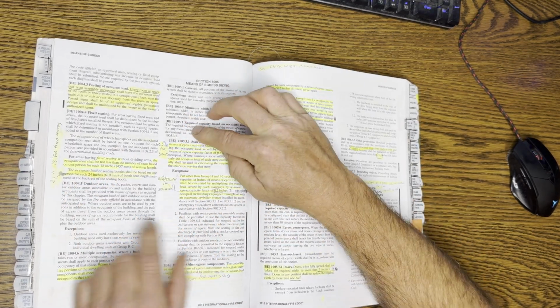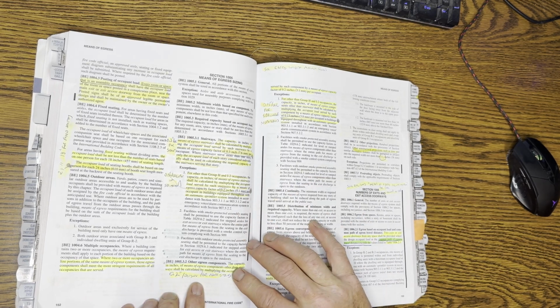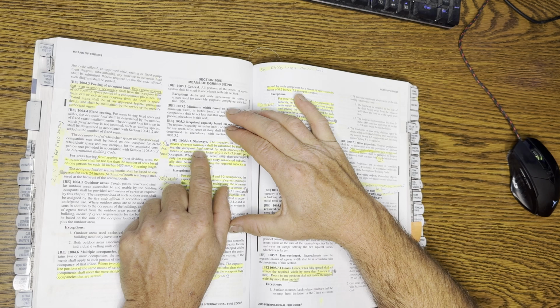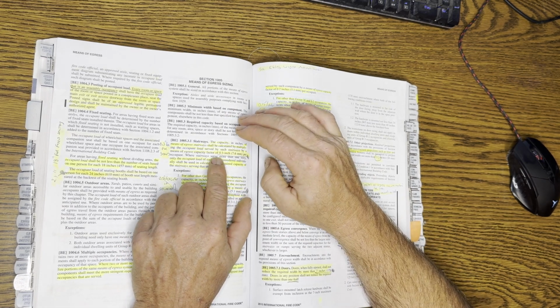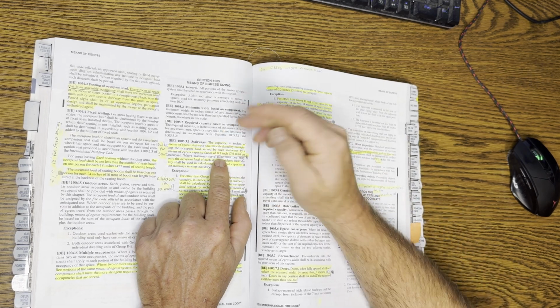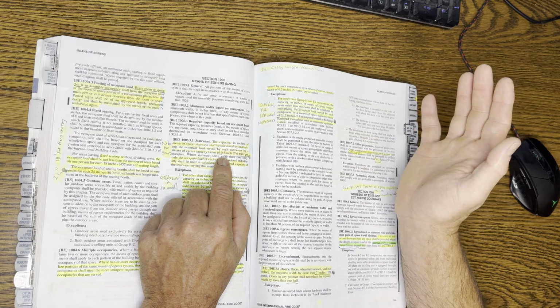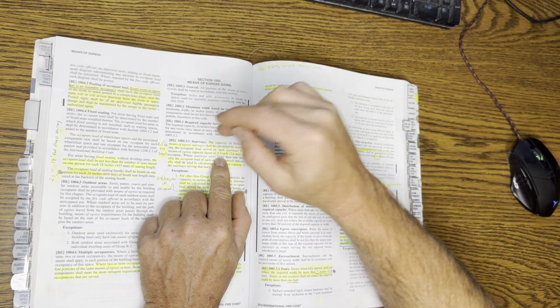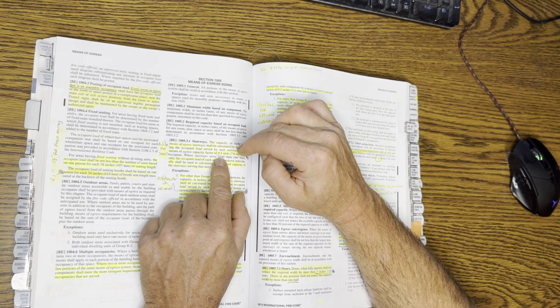Okay, stairway. I mentioned the 0.15 before for the door widths, but let me just explain this. If you're calculating stairway widths, in a suppressed building, it's 0.2. In an unsuppressed building, it's 0.3. Okay? What I mean by that is, let's say you have a 44-inch wide stairway. Let's say it's a non-suppressed building. So it's 44 divided by 0.3. That's how you calculate your occupant load.